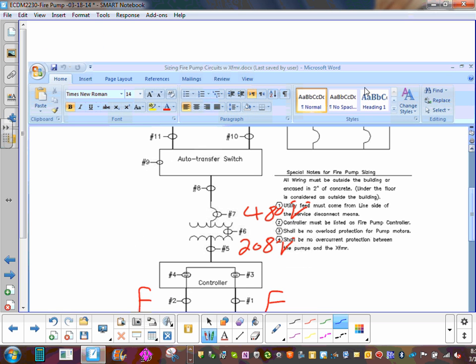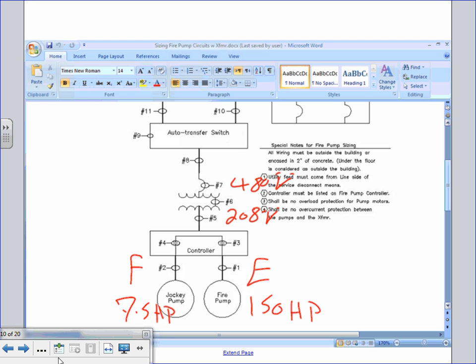All right, so let's go back to full. Okay, so now I do have a 480 system, the example, 208. It's an F code letter and an E code letter, and 7.5 horsepower and 150 horsepower. You guys see what the system that I have? The only difference is I stuck a transformer in between, right in here. There is a transformer in between. We're going to go size these. How many things now? 12 things? Or they still? Yeah, now 13 things. We're going to go size these 13 things. Shall we? Ready? Cool? Okay. So let's go start.